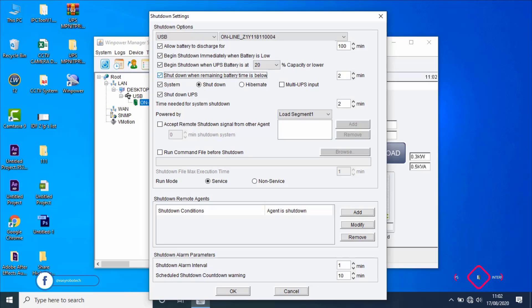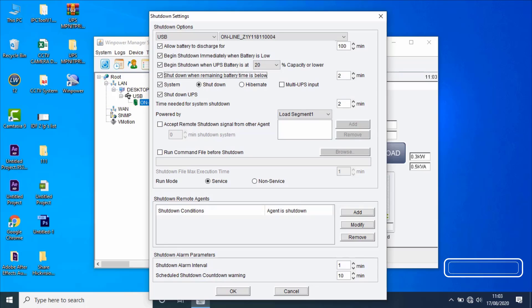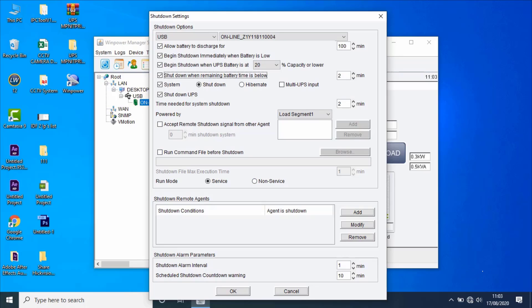When AC fails, software will inform the user that the input of UPS is abnormal. When UPS battery remaining time is below the setting value, software will send a shutdown command to UPS to protect systems and servers connected to UPS output, allowing them to shut down safely before UPS output is off. Software can shut down the local computer communicating with UPS, and also can shut down the remote computer whose input is connected to UPS output, to safely shutdown before UPS output is off.